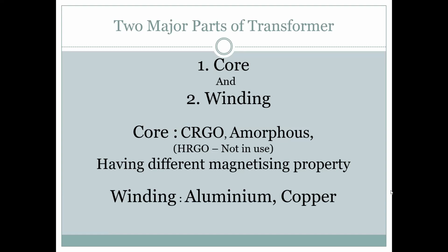And the next generation is amorphous. Amorphous has still not come in a big way. It is basically the alloy steels, the CRGO, and amorphous is not steel, it is some other material. Amorphous is not being used for large transformers, but for small distribution transformers it is still being tried out, and in some electricity boards amorphous metal is used in small distribution transformers.